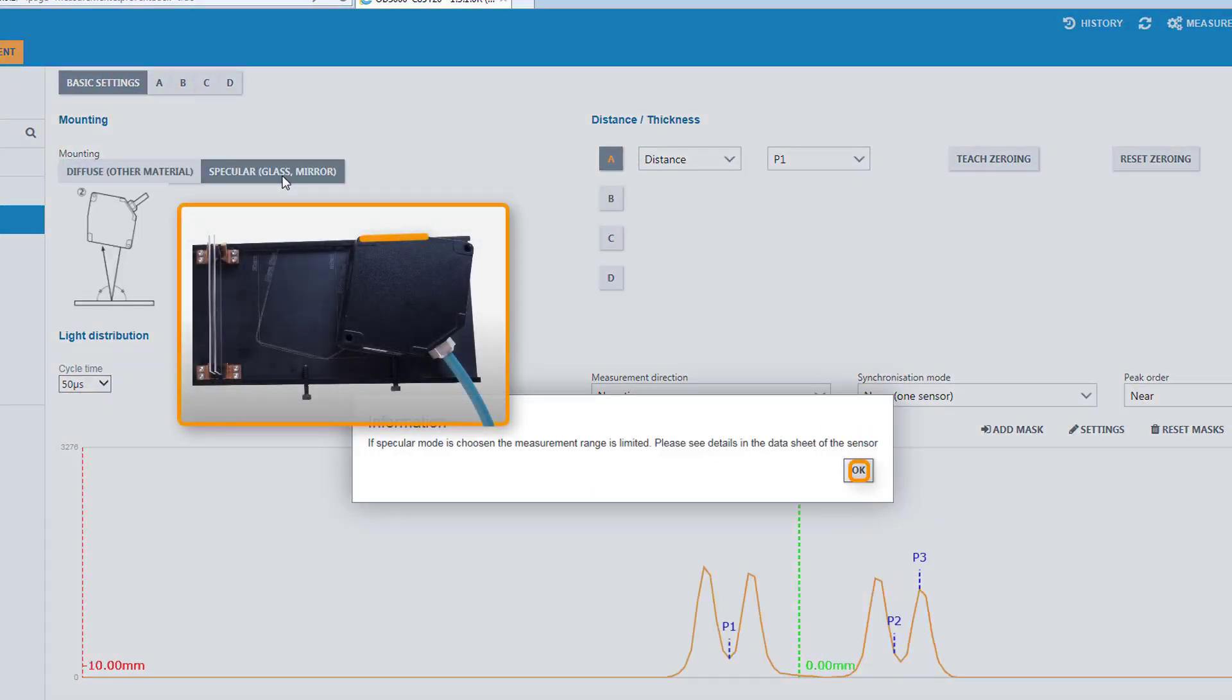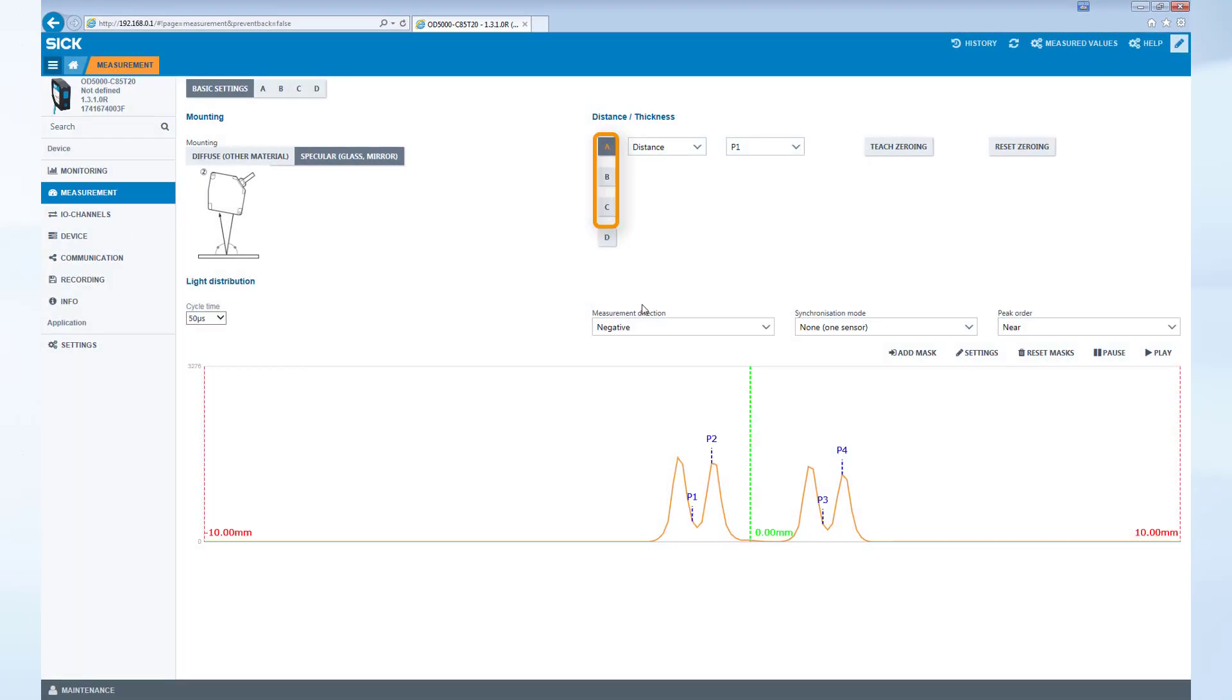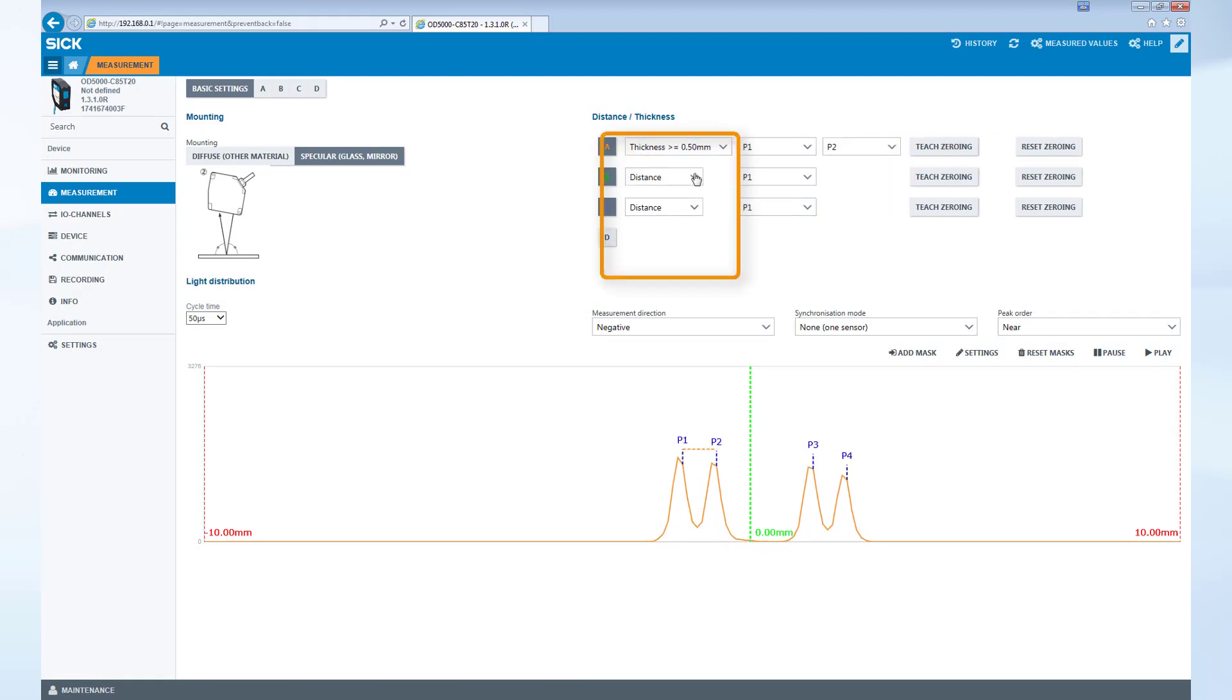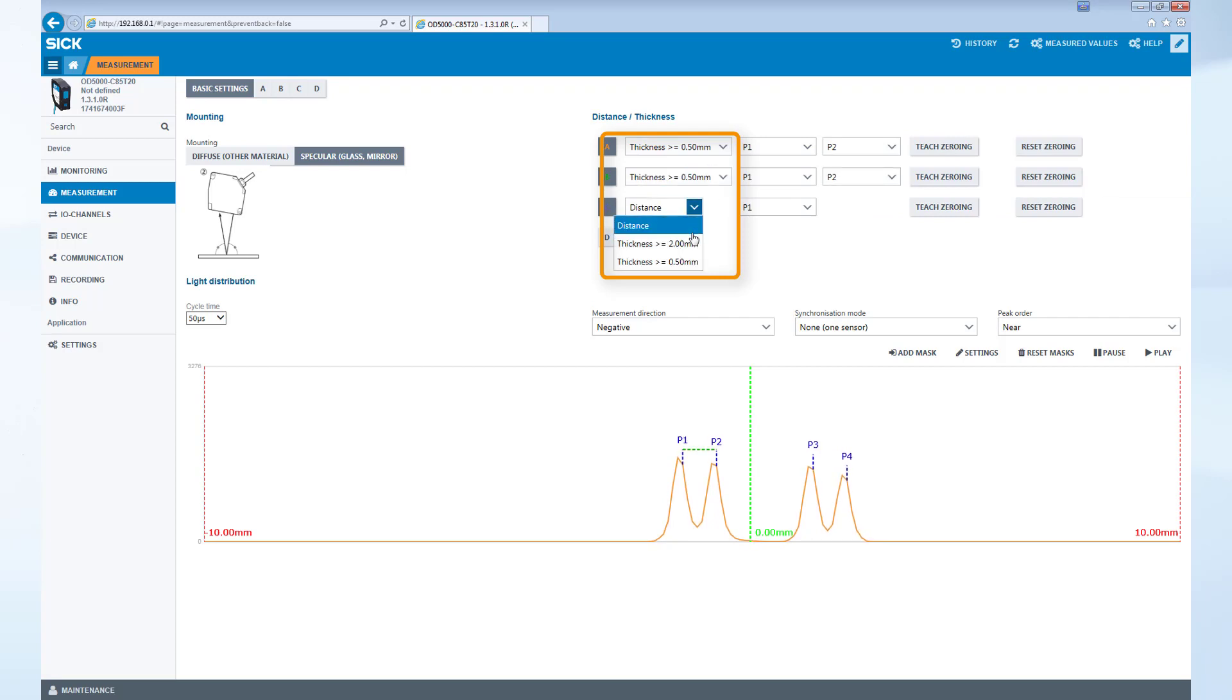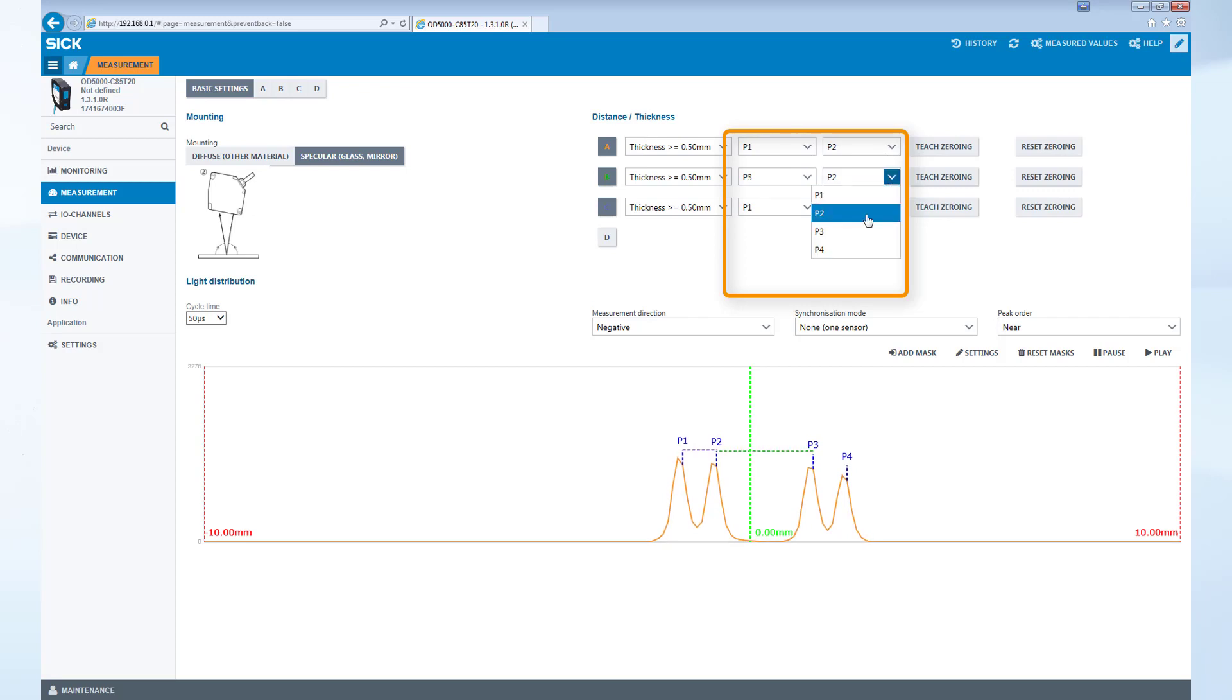Make sure the sensor is mounted for glass thickness measurement. Activate two more channels by selecting the letters B and C and choose the measurement function thickness equal to or greater than 0.5 mm and the corresponding peaks for all three channels. Peaks one through four represents the transition from air to glass and glass to air.